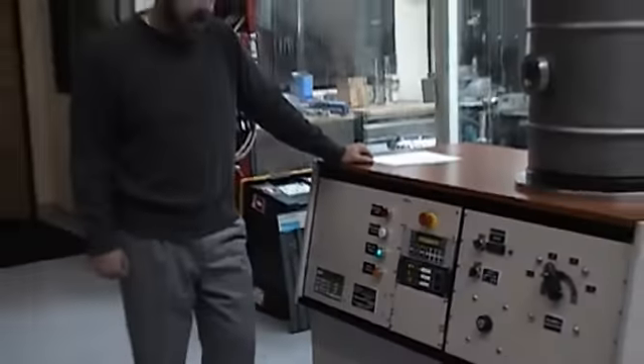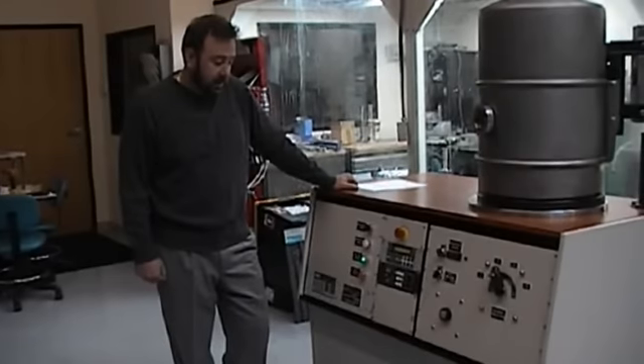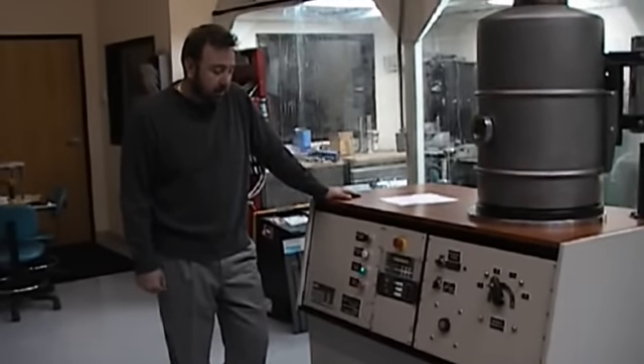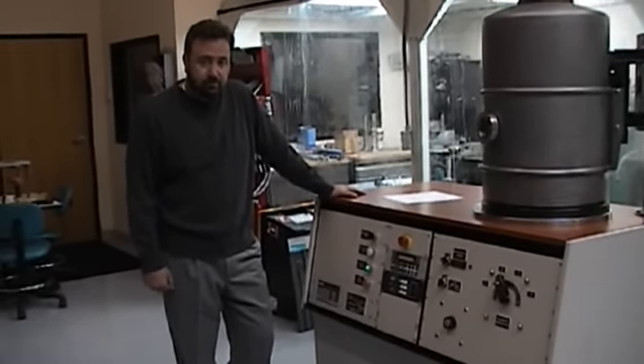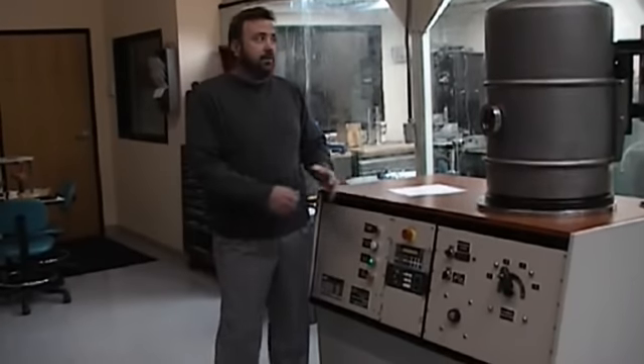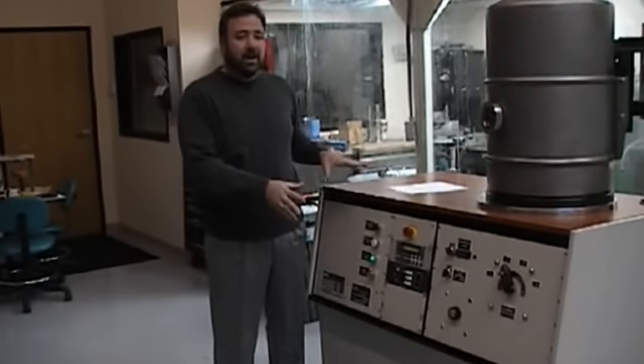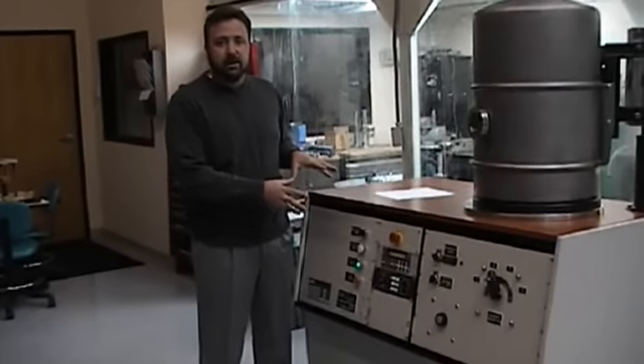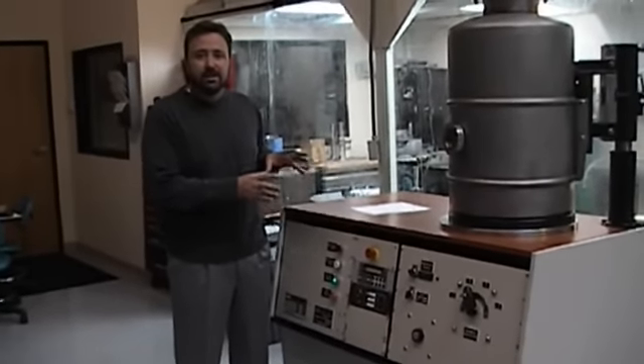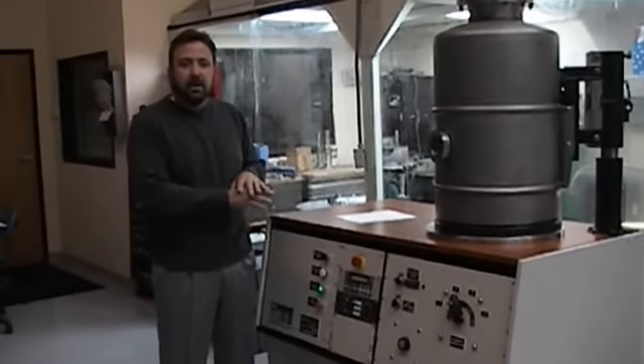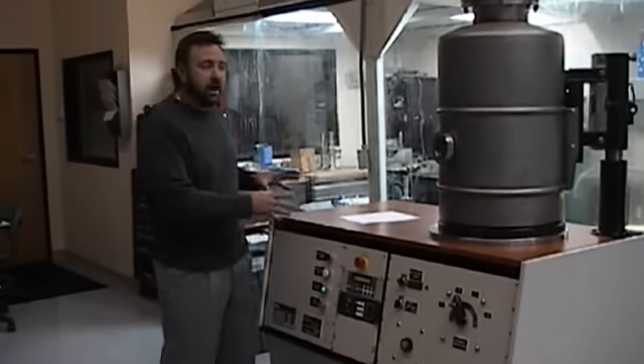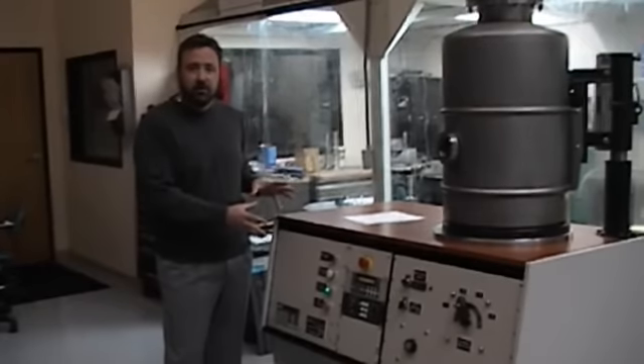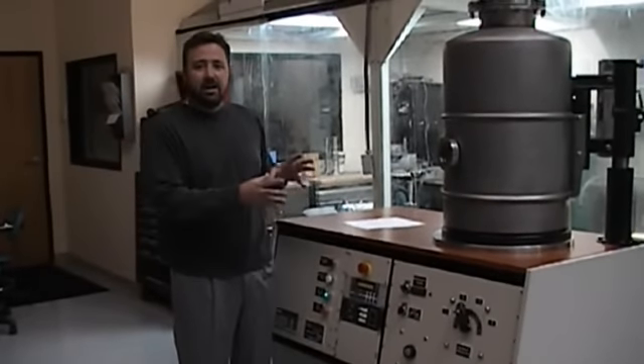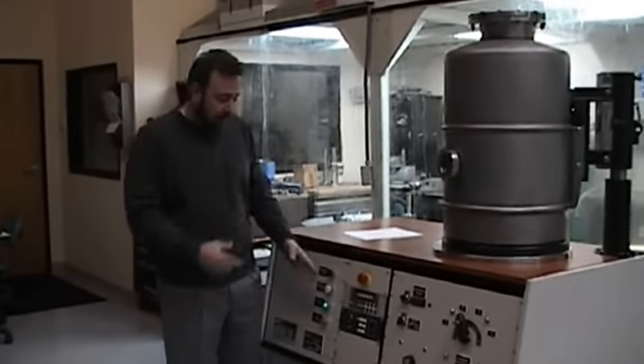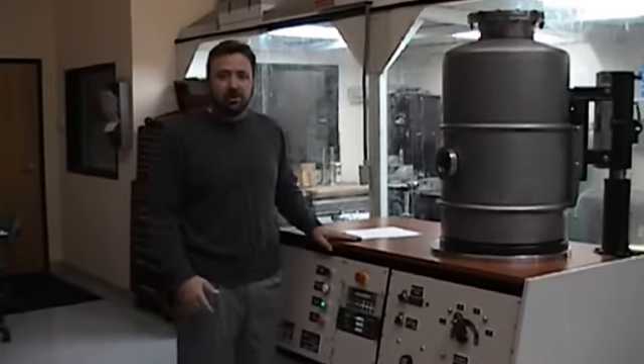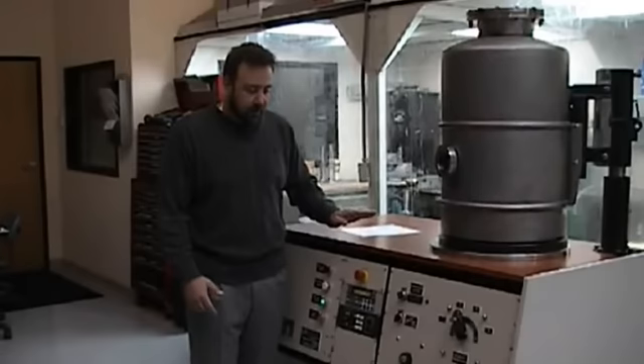Right now we're at 8 times 10 to the -6. If left to pump alone, it should go down quite a bit further. The plate vacuum system has been helium leak tested to 1 times 10 to the -8 standard cc's of helium. It is tight. We are not going to demonstrate that, but we will certify on this video that it is leak tight. If it wasn't, we would not be able to achieve the pressures that you're witnessing.